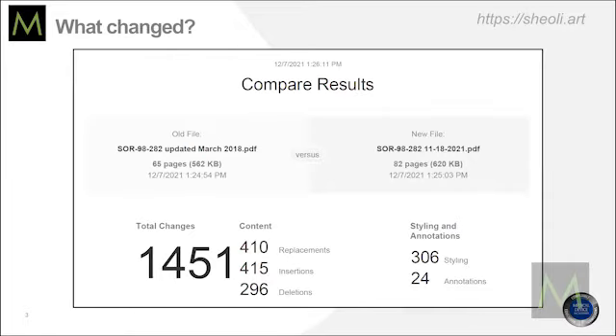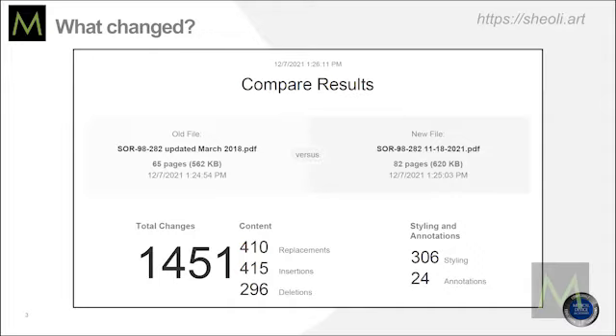Any MDSAP auditor will know what to look for. If people are not familiar with Canadian regulations, there is now a requirement for MDSAP certification in Canada — it's been around for many years, at least five. MDSAP is an acronym for Medical Device Single Audit Program. The goal was to have one audit that covers all the countries in the world. Only certain countries have opted in: the US, Canada, Brazil, Australia, and Japan. But Canada is the only one that absolutely requires it — you cannot even apply for a license to distribute product in Canada without it.